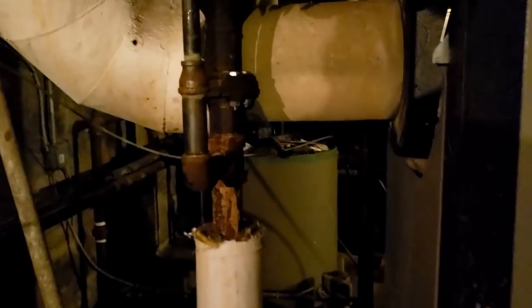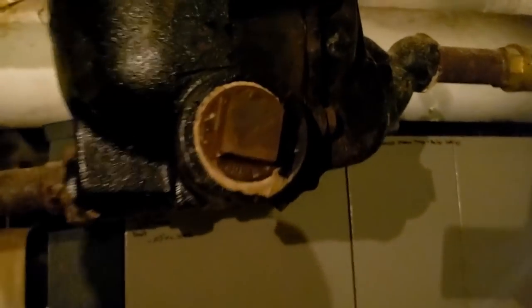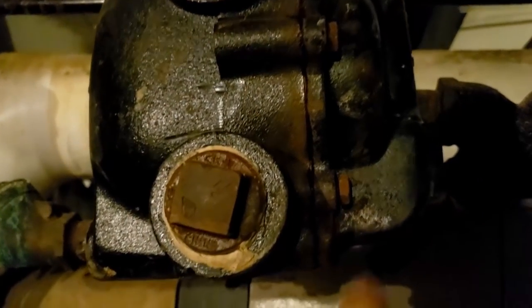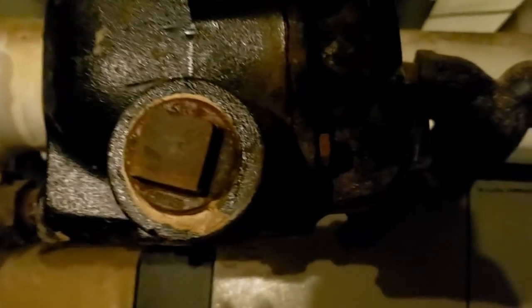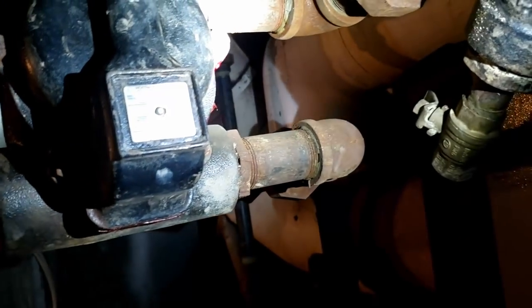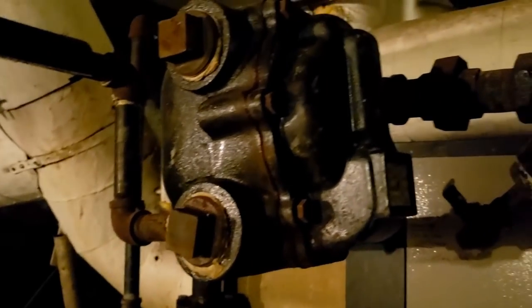This thing's kind of a dungeon down here. She's running, comes up through the check valve, comes up over all the way across and down into the back side of the boiler here, and then fills into there. You can see where I took this one apart, had to build a gasket for it, which is this. Kind of curious how that turned out. Kind of hadn't really used it before. It's a Loctite gasket maker. Kind of still feels a little sticky, but it's not leaking, which is nice.